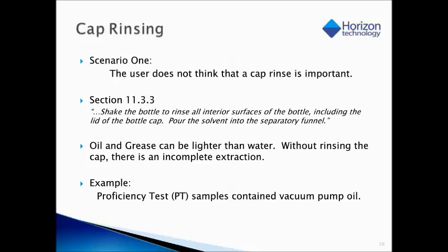So let me give you an example. A few years ago, there was a company that was selling proficiency samples that had vacuum pump oil rather than the hexadecane and stearic acid mix that we typically use for our LCS style samples. When you would get calls, the underlying problem for low recoveries would end up being not rinsing this bottle cap that was received in. And we could see impacts in the final recoveries as much as 10% or more in some cases, depending on how bad that cap was coated.